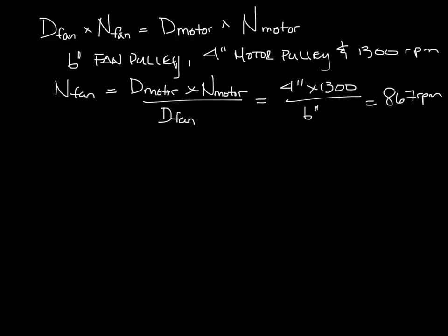So you can calculate the new CFM using the fan laws. Or more likely, you'll use the fan laws to calculate the RPM you need because you know the CFM you need. So let's say you are getting 2000 CFM at your 867 RPM fan, but you need 2400 CFM out of your fan.